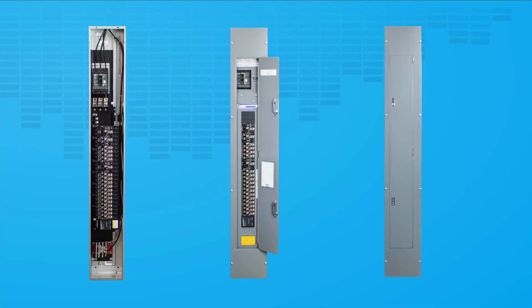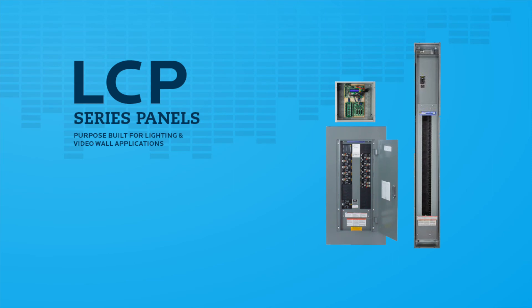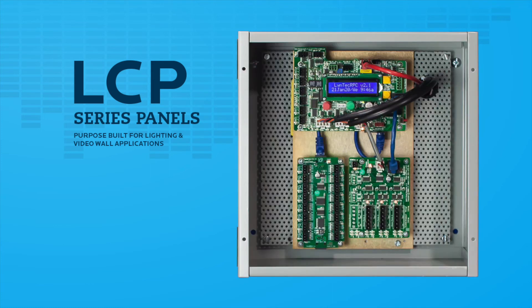The LCP Series is also now compatible with Lyntec's new narrow panel configuration for increased project cost savings or for use when horizontal or vertical wall space is at a premium. Thanks to the change in hardware platform, the LCP now utilizes an external enclosure for its control board and low-voltage electronics for more flexible installations. The external enclosure is a 12-inch by 12-inch by 4-inch enclosure and needs to be installed in the same room as the main LCP control panel, but is not directly attached to it.